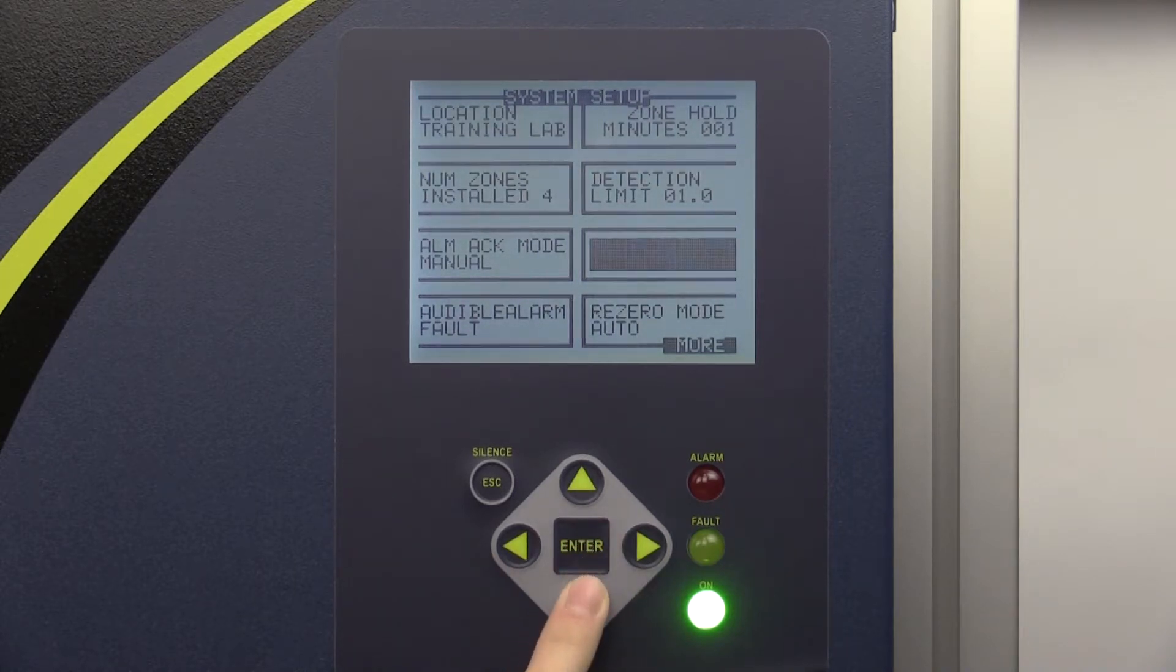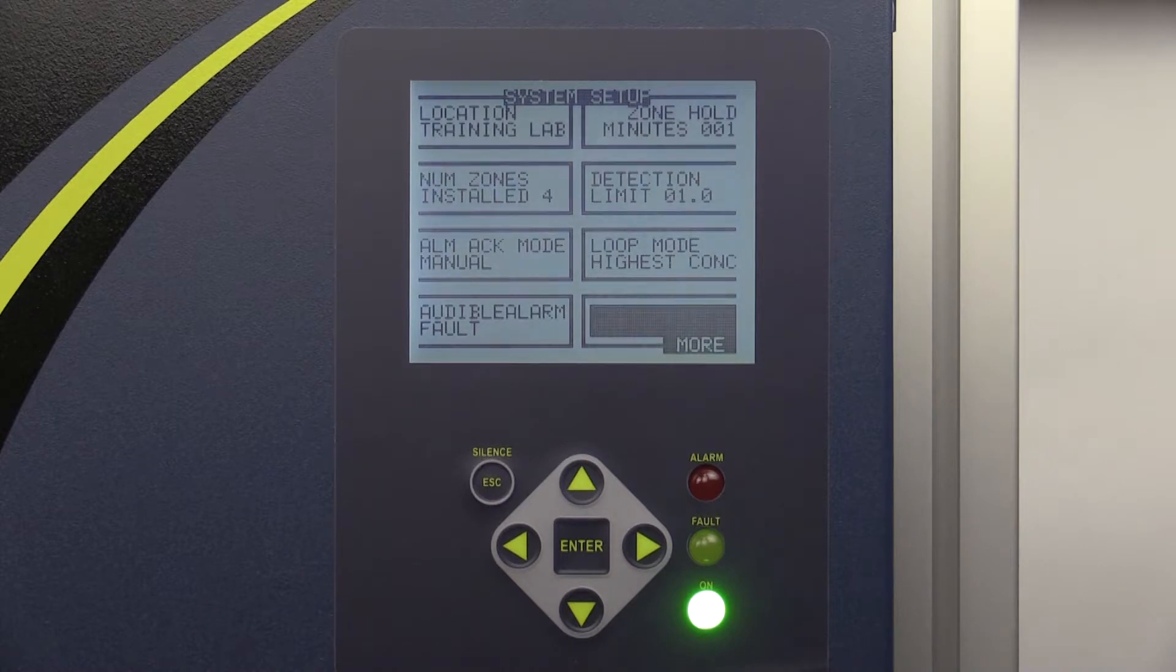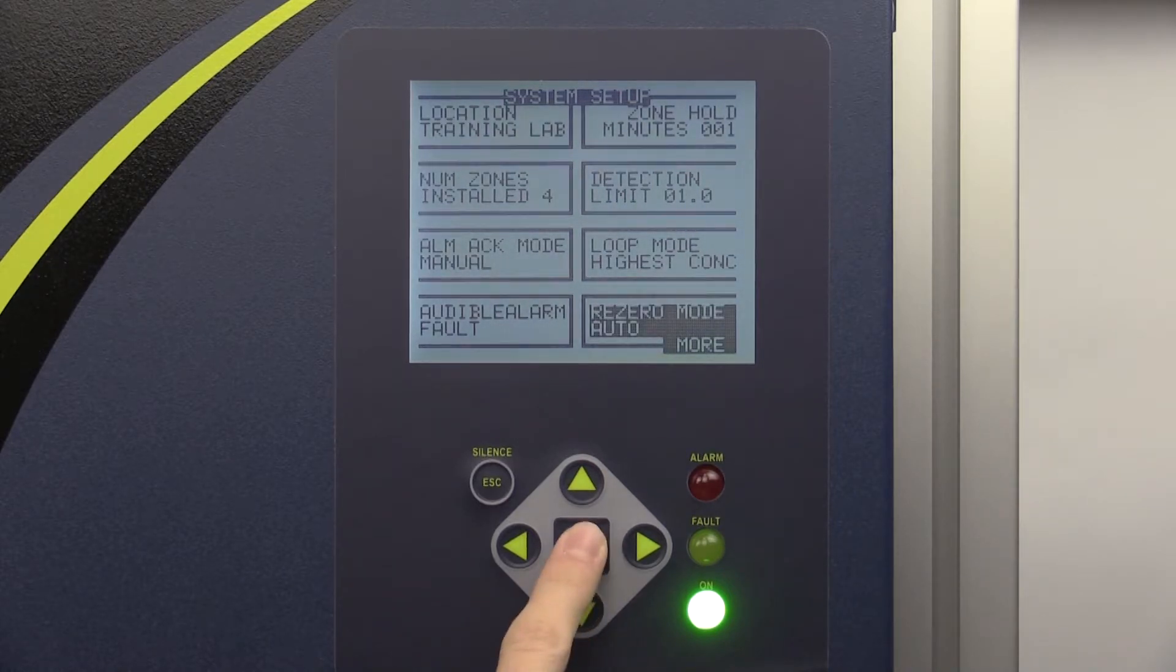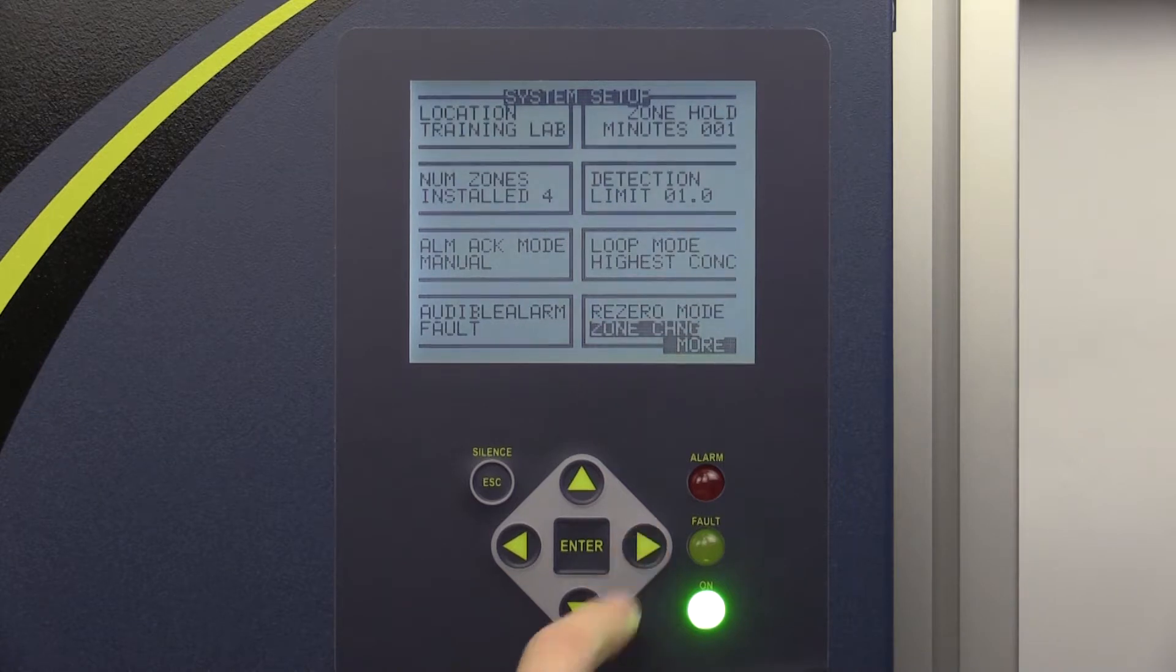The ReZero mode tab allows you to set the frequency at which the device recalibrates the optical sensor. The Auto option will recalibrate the sensor every 10 minutes. The Zone Change option will recalibrate the sensor at every zone change. The Zone Change option is the most accurate setting, but it increases the time interval between measurement cycles.